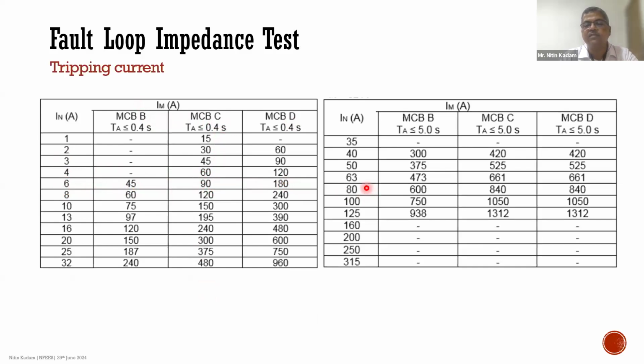If you have a 63 amp MCB, in that case, for type B, it should be more than 473. Type C, it should be more than 661. And type D also, it is more than 661. So when you do this test, this chart should be available with you, and the values should be noted down when you do the test, and the value should be higher than the test values that are given there.